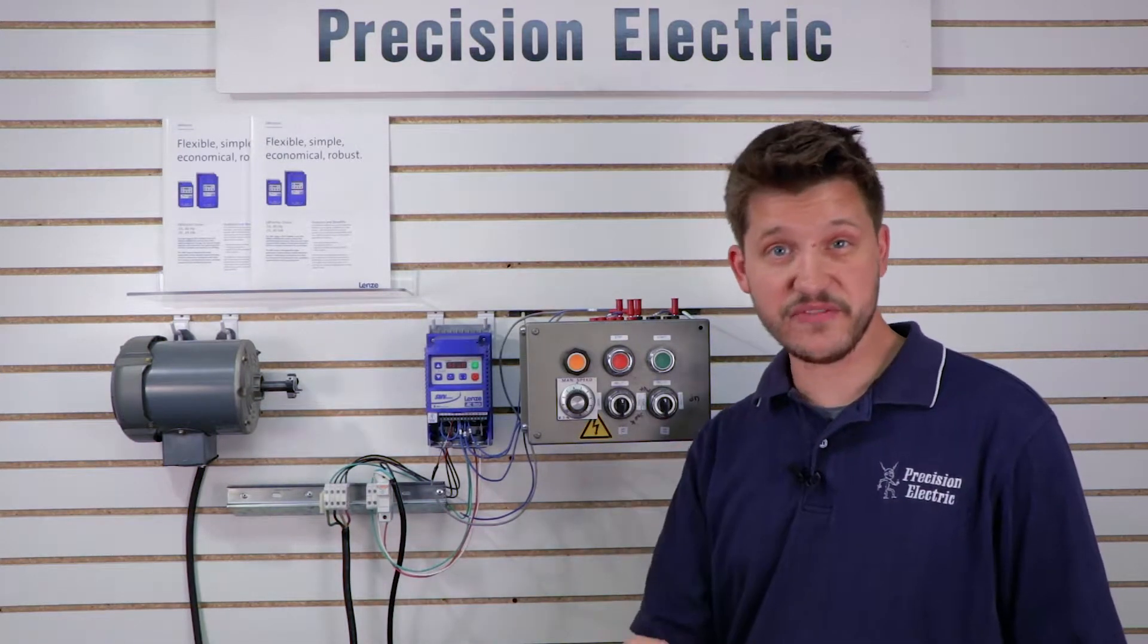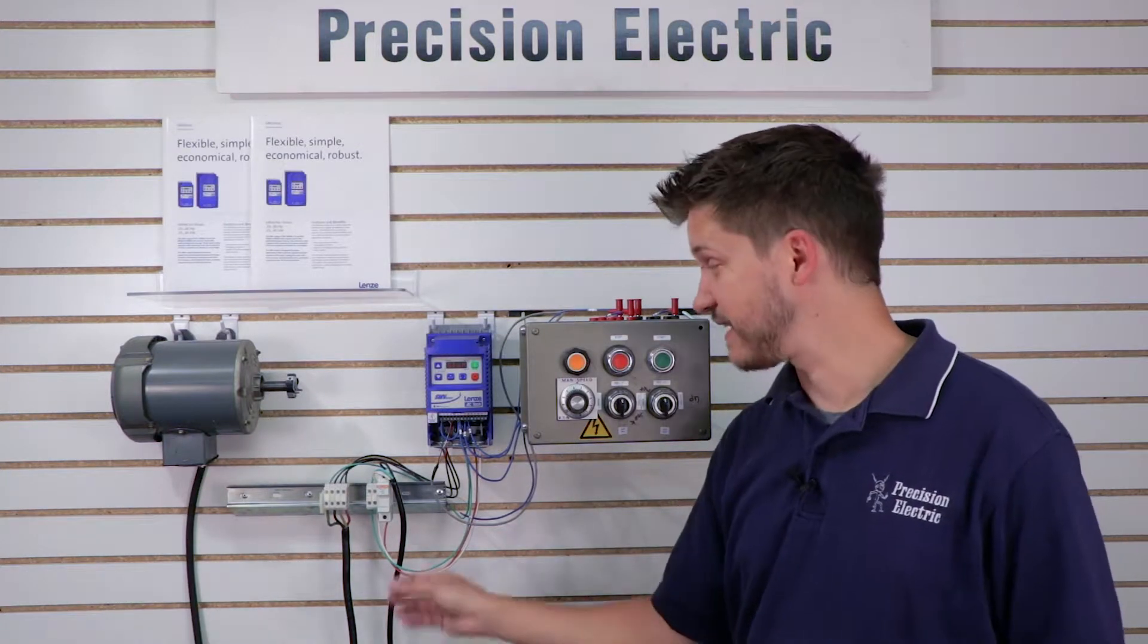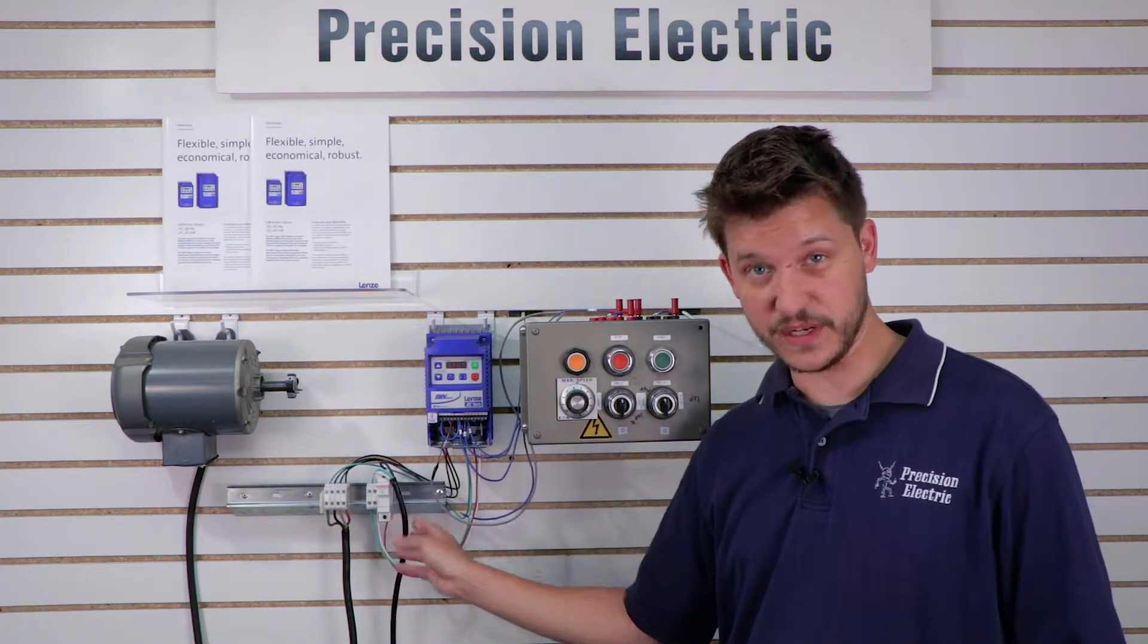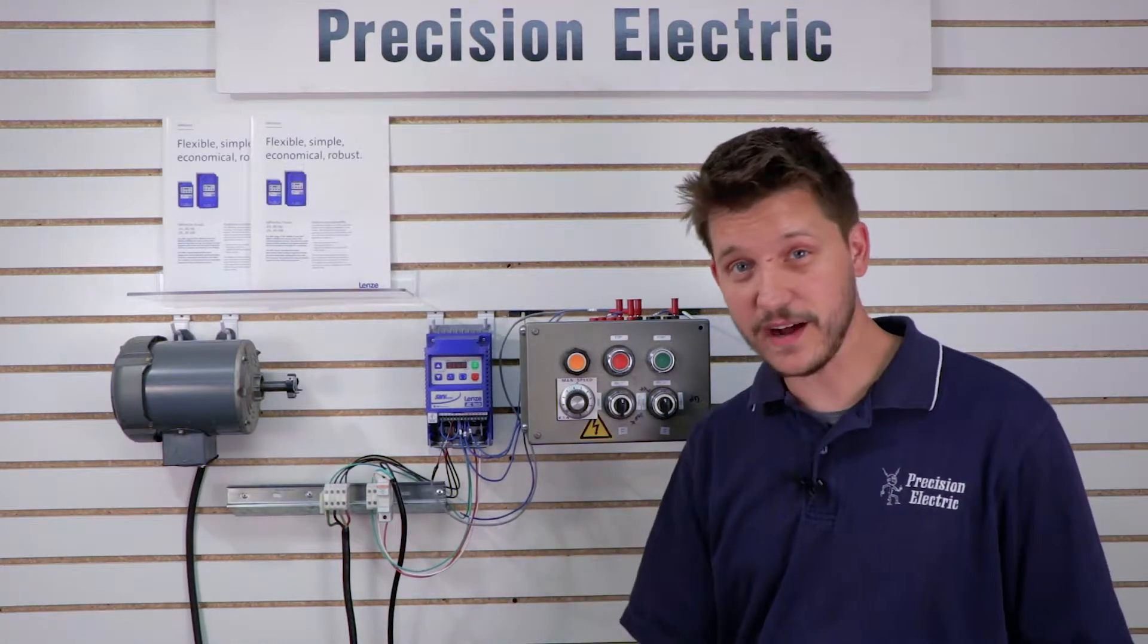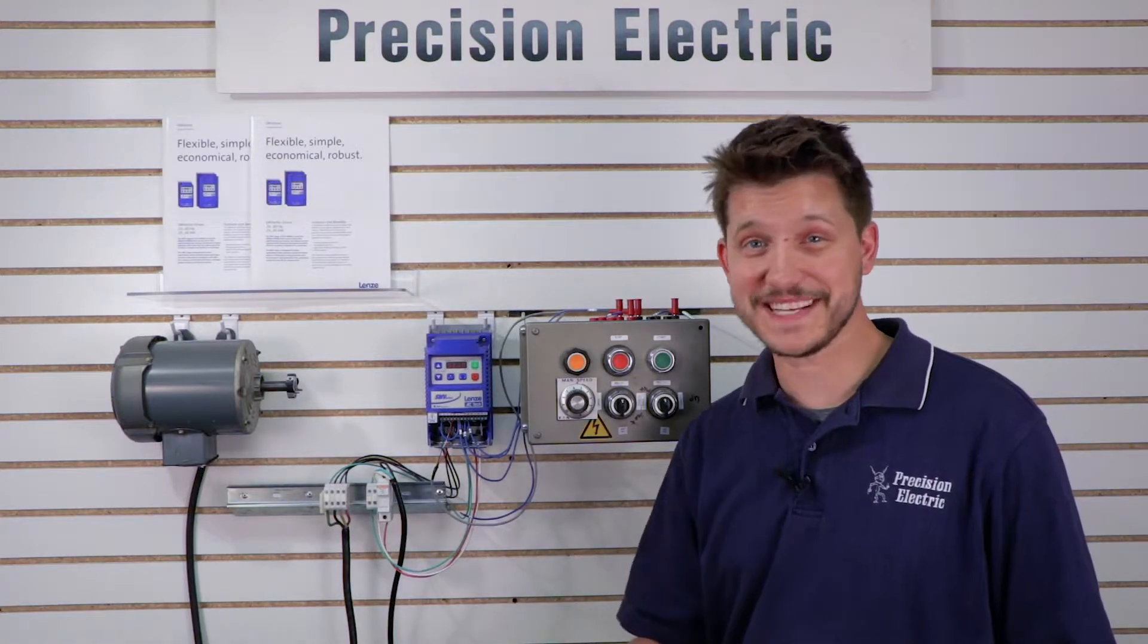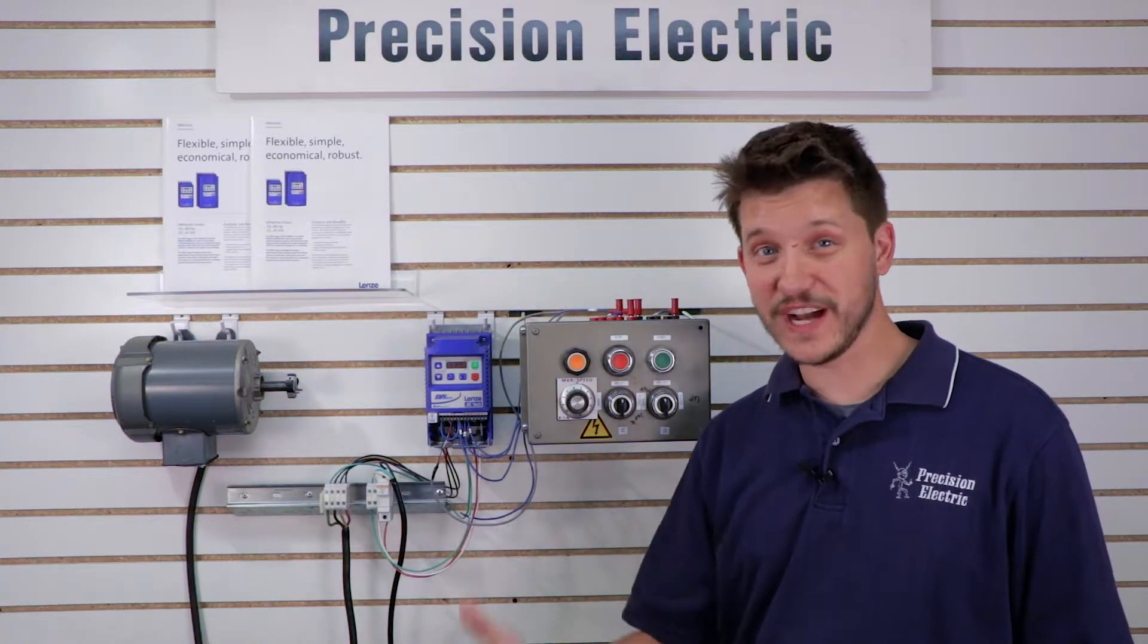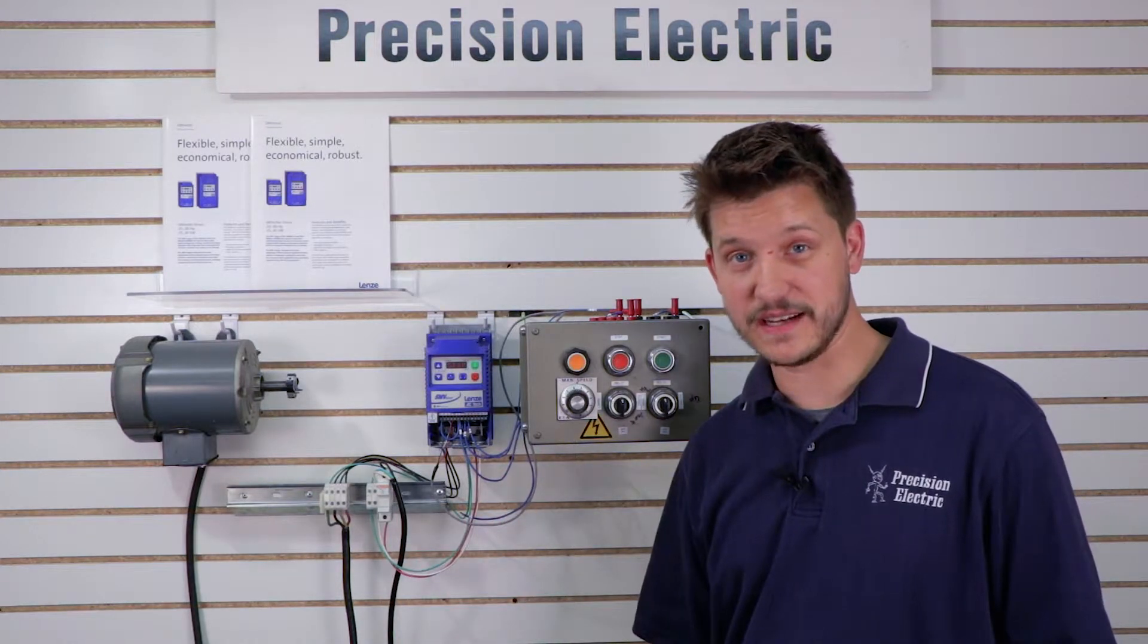If I've got three phase 230 volt or three phase 460 or three phase 600 volt, then I have to fuse all three because all three of them are hot. Essentially anytime there's a hot wire you have to fuse it. It's absolute minimum requirement. You'd be amazed at how many people call and their drive blew up and we find out they didn't even have a fuse or a breaker on the line side.